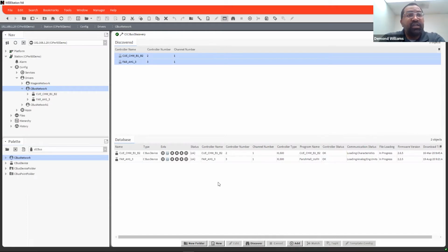What this is doing is it's going out, grabbing any schedules, any parameters, alarms, all the text engineering units, or everything that is actually in that controller at that time. It's actually uploading all of that on its own. So give it about a minute or two before you actually touch or move on from here. If you do at this time try to go and discover any data points, it will come back that it did not find anything. So you want to make sure right here where it says communicating status that it is actually finished and not saying loading.